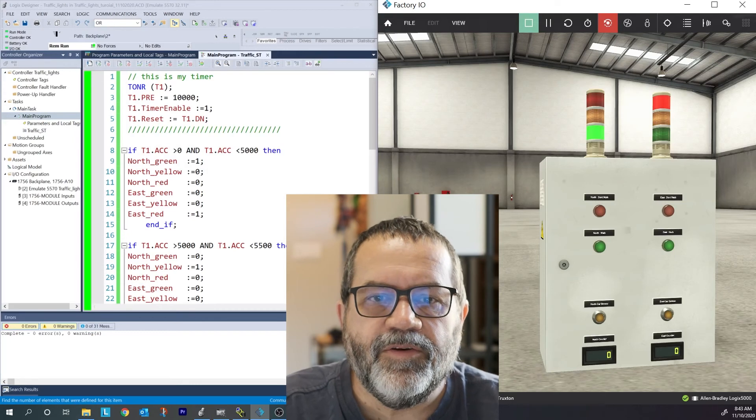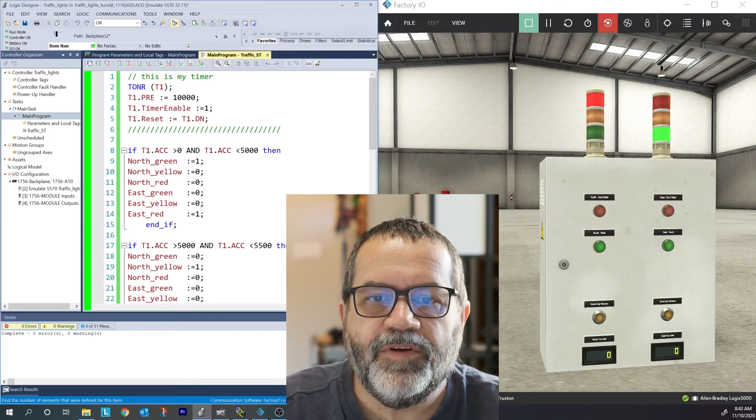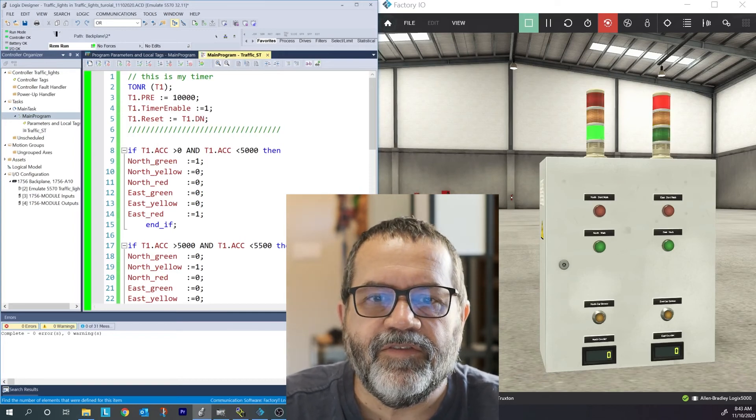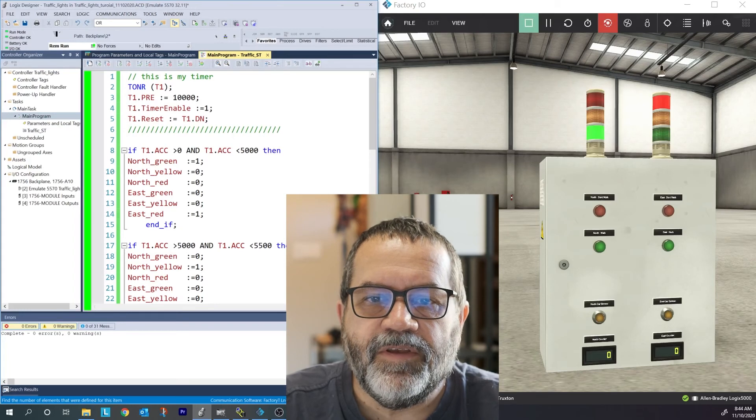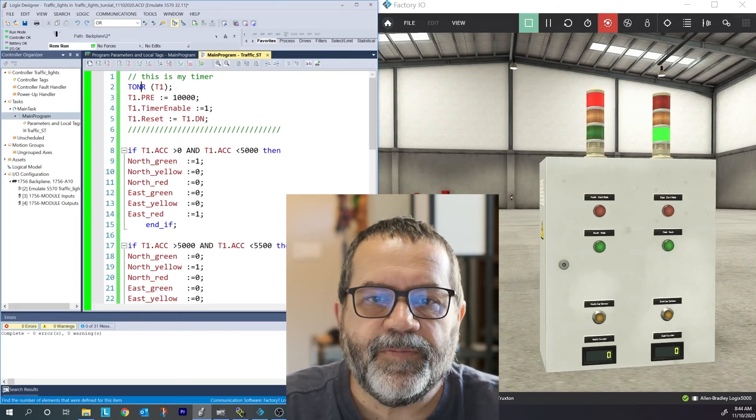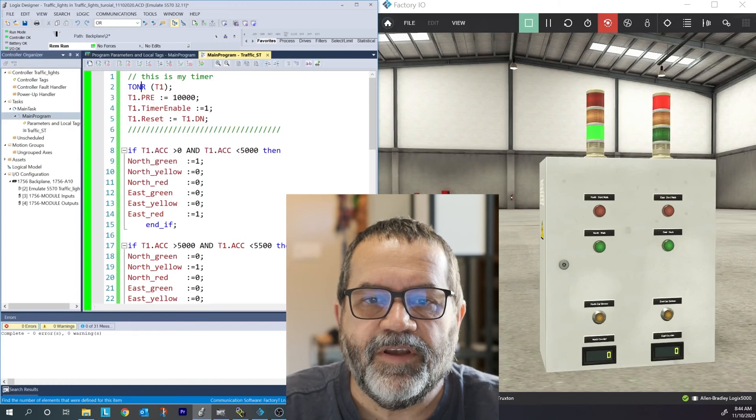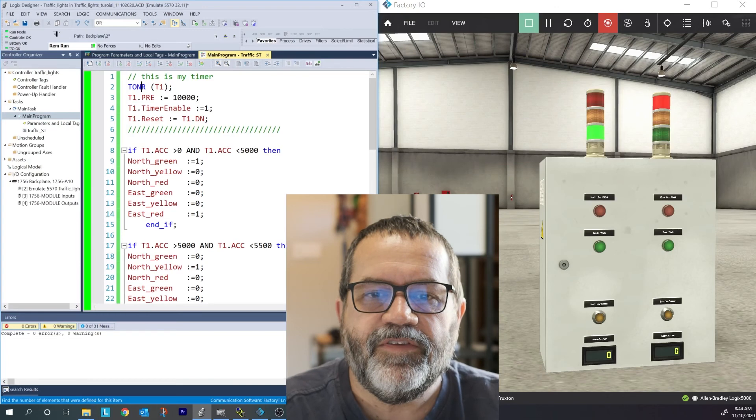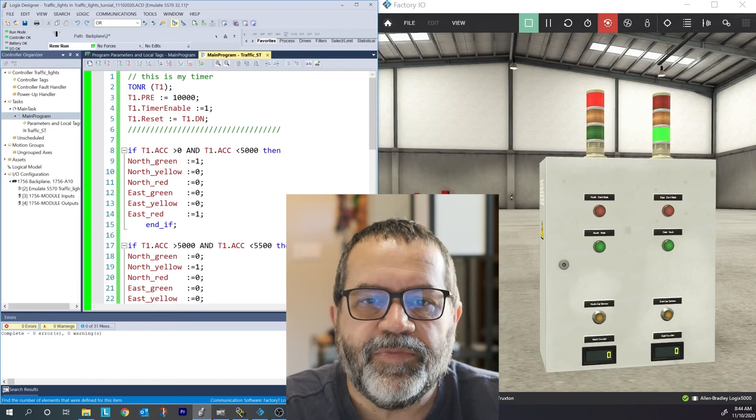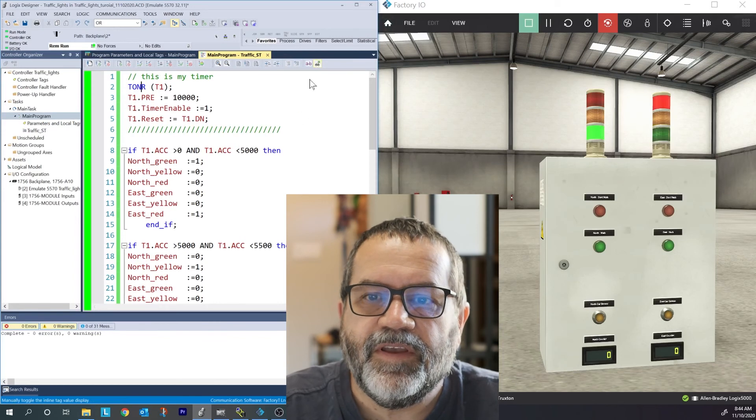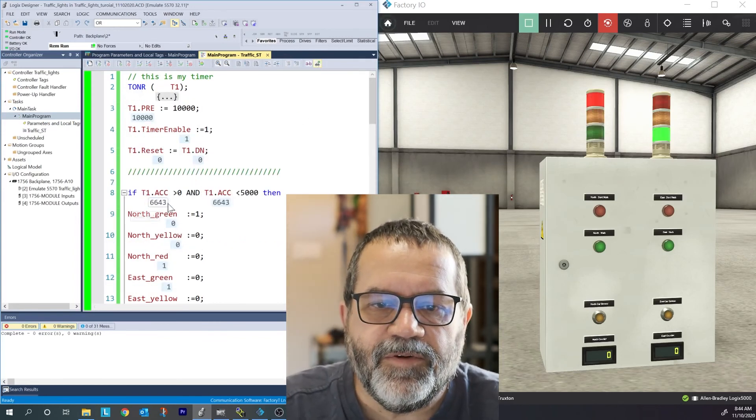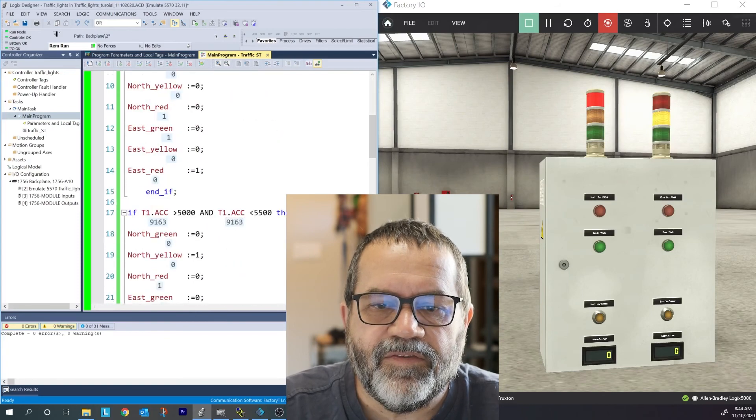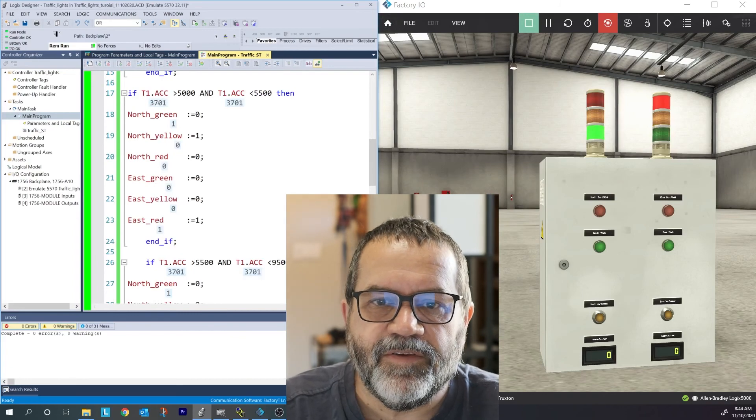Over here, I tell it I want to use a timer. I put in my timer preset. I use 10 seconds, you can use whatever you want. My timer enable is locked on so that timer never stops. And my reset is my done bit. So as soon as that timer gets up to 10 seconds, it resets and it starts over. So this timer always runs. And if I show my tags, down here I can see my timer timing and I can see the different values changing on my output tags.